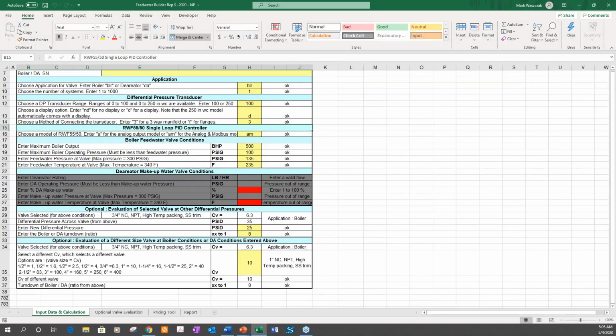Now for a feed water builder program, I've already taken the time to fill out the information to save on time. So very similar to the other sizing programs we did. With this one, you select whether you have a boiler or DA, how many systems you're looking at. Choose the DP transducer range, usually 100 inches suffices. Whether you want a display or no display on the DP transducer, the only difference here is what type of cover they have on there. If you choose no display, it's a solid metal cover. If you choose a display, it's a metal cover with a glass insert.